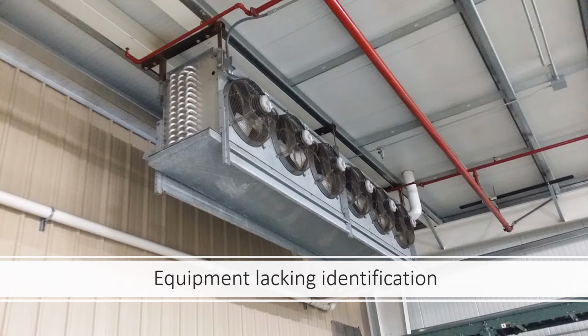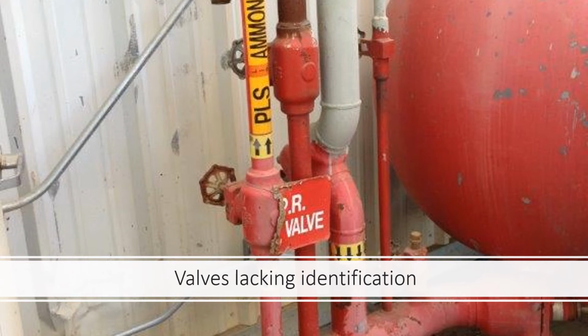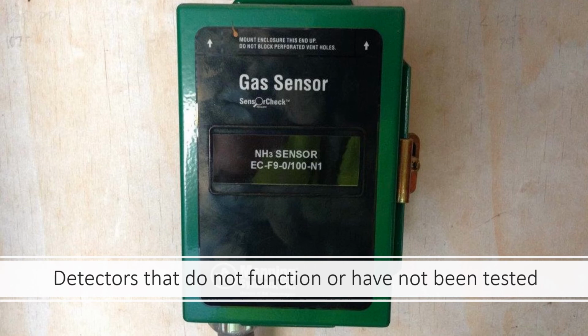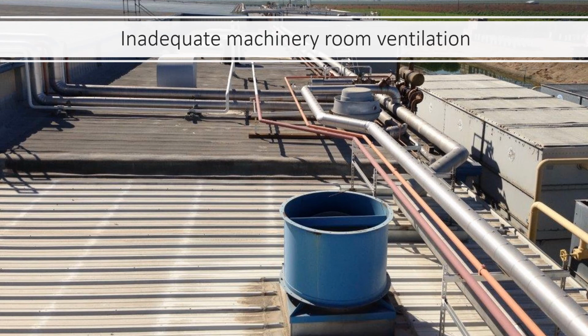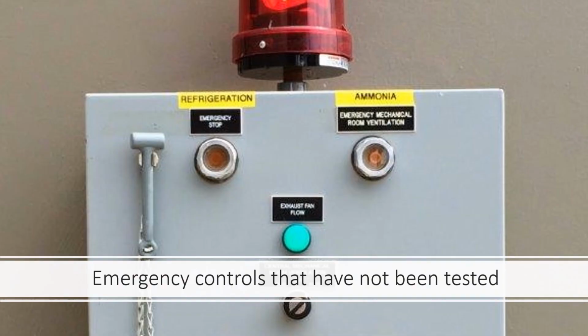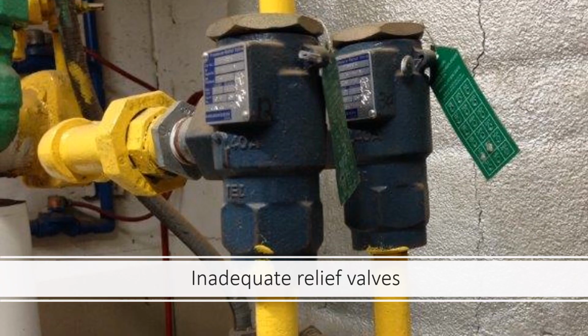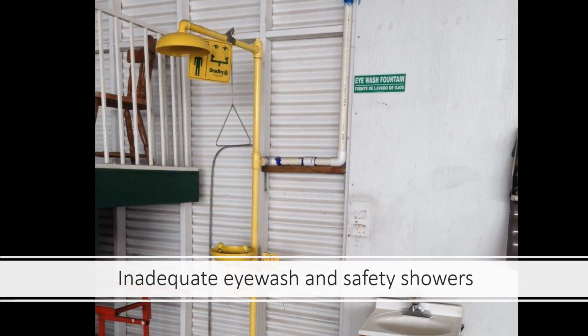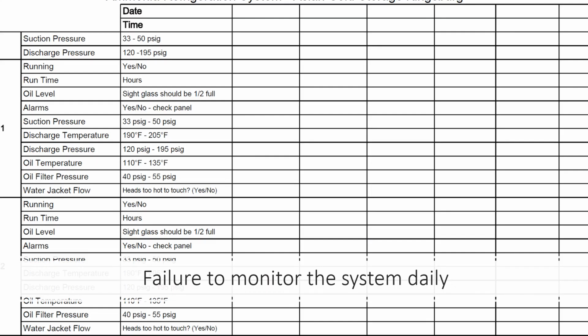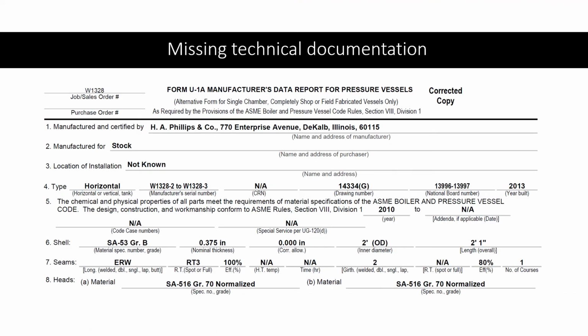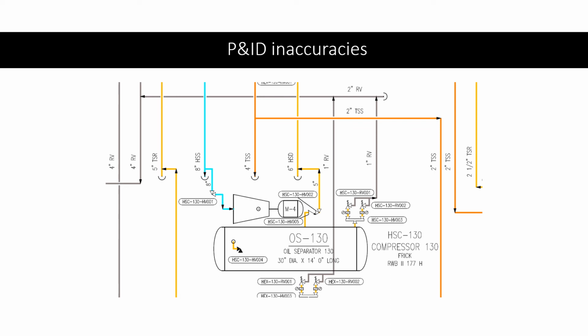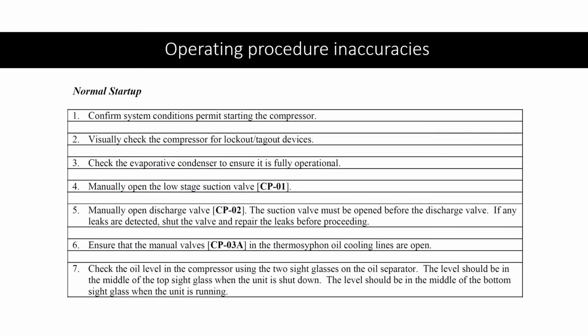equipment that lacks proper identification, important valves such as king valves lacking identification, gas detectors that are not functional or have not been calibrated per manufacturer's recommendations, ventilation systems with inadequate airflow or systems that have not been interlocked with detection, emergency controls that have not been tested, relief valves that are undersized, the incorrect set pressure, or haven't been replaced within the last 5 years, eyewash and safety showers that are not installed, don't have adequate water flow, or aren't located in close enough proximity to the system, failure to monitor the system daily, facilities that have not obtained important technical documentation, such as manufacturer data reports, P&IDs that contain inaccuracies, and SOPs that do not reflect the actual practice of the facility operators.